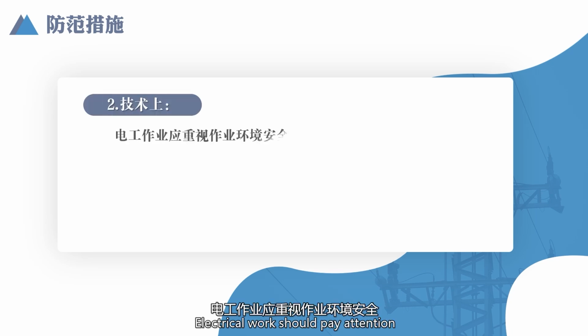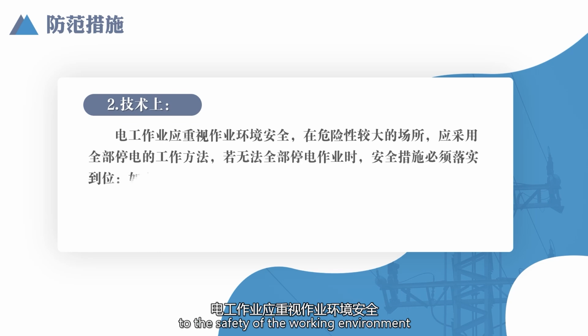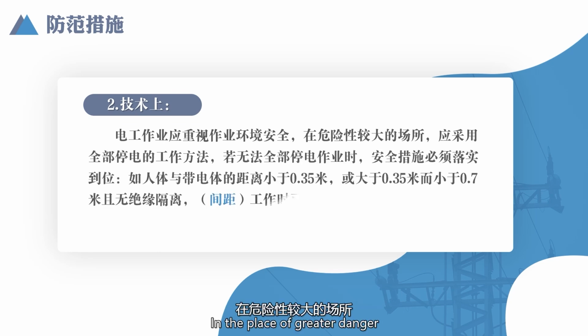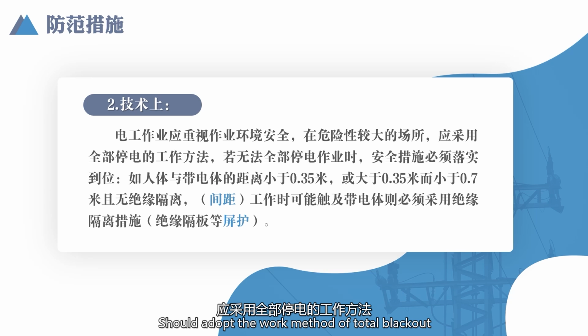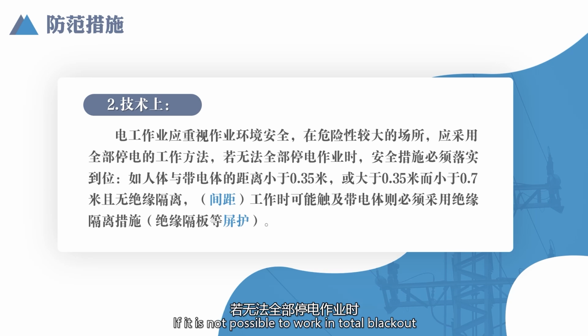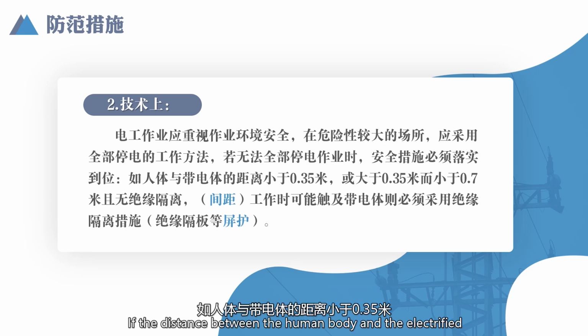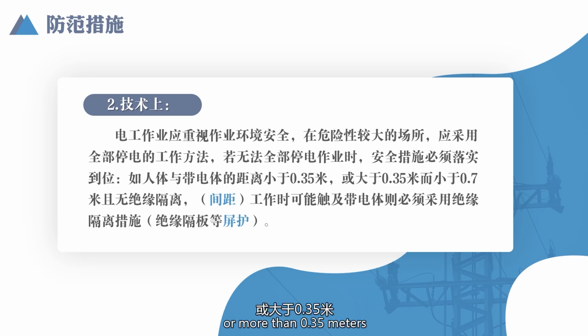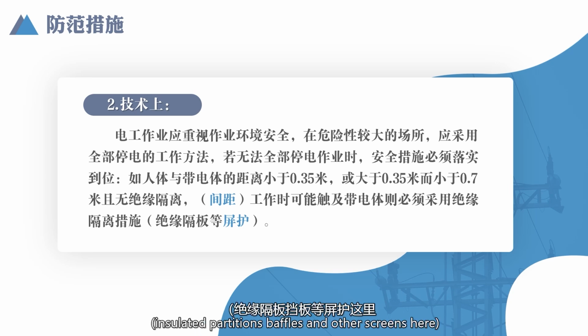2. Technically, electrical work should pay attention to the safety of the working environment. In the place of greater danger, should adopt the work method of total blackout. If it is not possible to work in total blackout, safety measures must be put in place. If the distance between the human body and the electrified body is less than 0.35 meters, or more than 0.35 meters and less than 0.7 meters without isolation, spacing work may touch the charged body, insulation measures must be used.